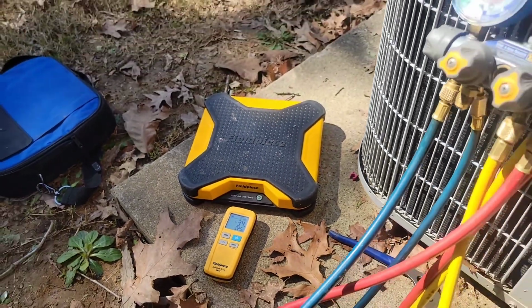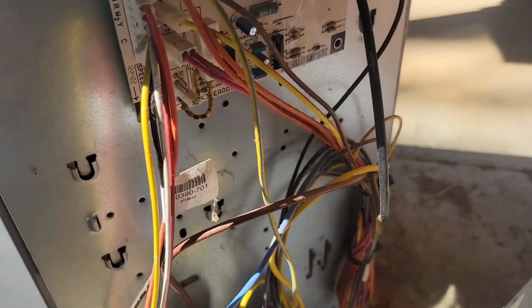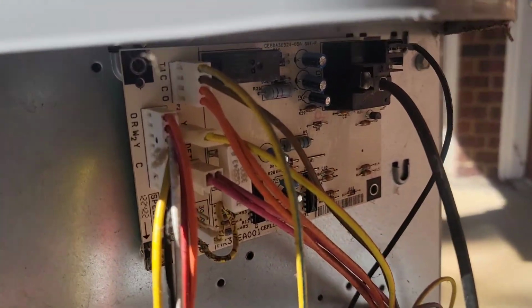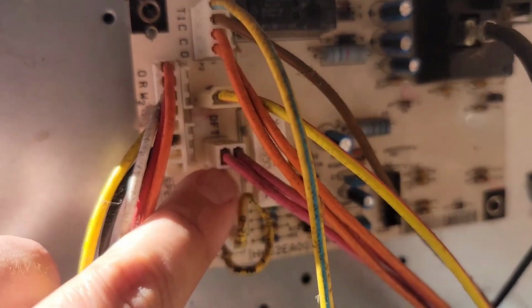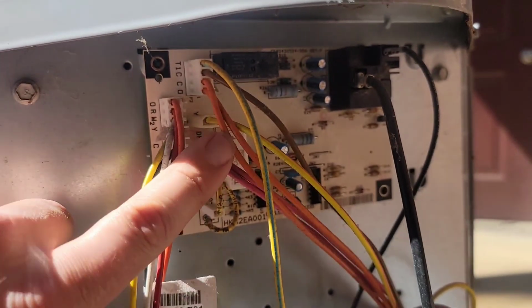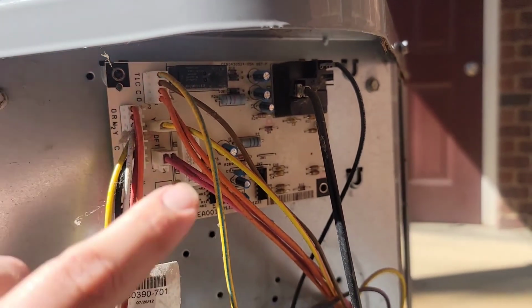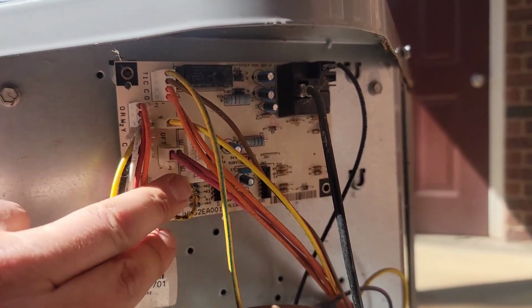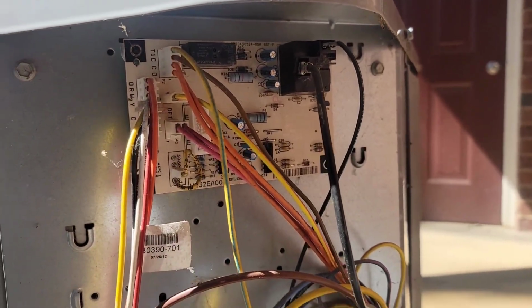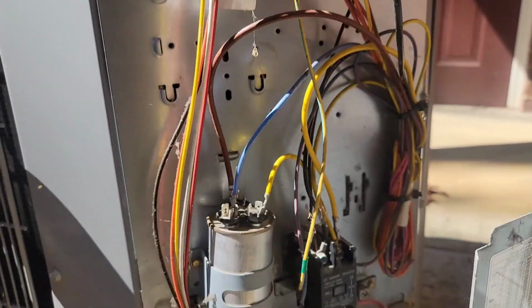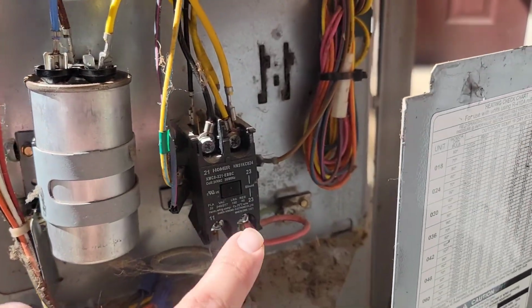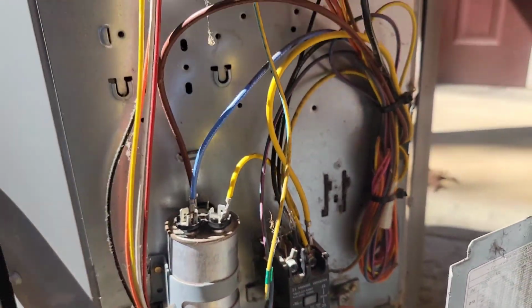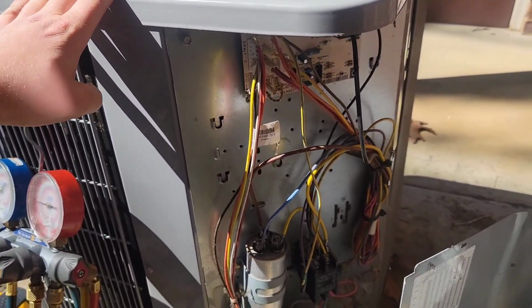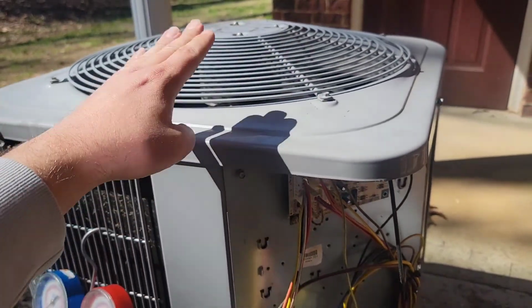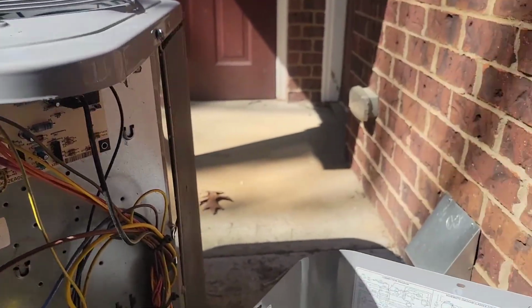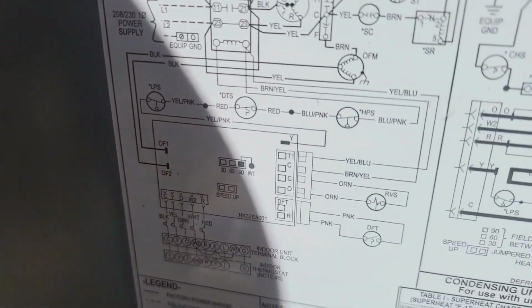They're really nice. So, outdoor unit. This is a heat pump, so we've got a defrost board. DFT means defrost thermostat. If you don't know how to test a defrost thermostat, I'll put a link in the description. If you don't know how to find out if a defrost board's bad, I will put that in the link in the description as well. Got a dual capacitor, got a 2-pole contactor, and that's about it for this equipment. Pretty easy, and it's got a couple pressure switches, low pressure and high pressure.